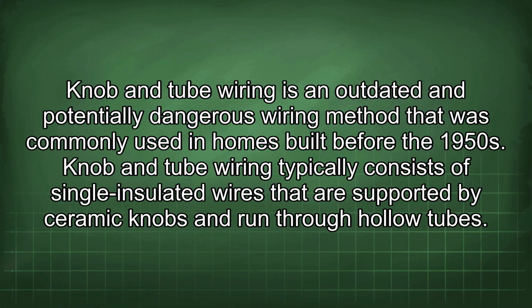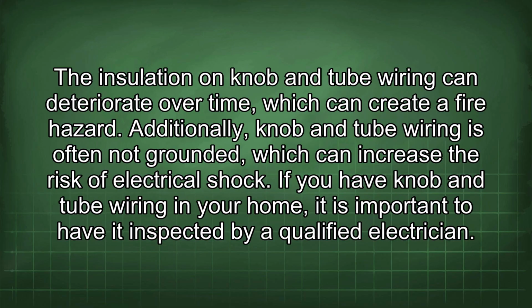Knob and tube wiring is an outdated and potentially dangerous wiring method that was commonly used in homes built before the 1950s. Knob and tube wiring typically consists of single insulated wires that are supported by ceramic knobs and run through hollow tubes. The insulation on knob and tube wiring can deteriorate over time, which can create a fire hazard. Additionally, knob and tube wiring is often not grounded, which can increase the risk of electrical shock.